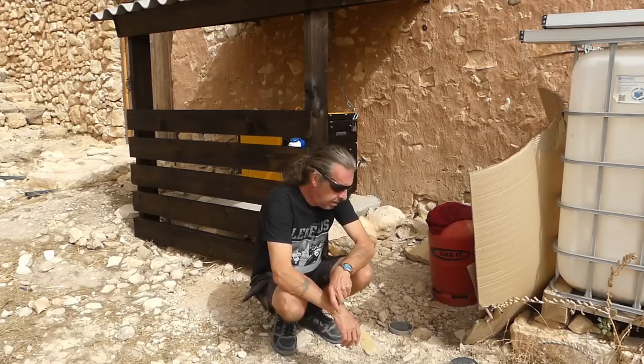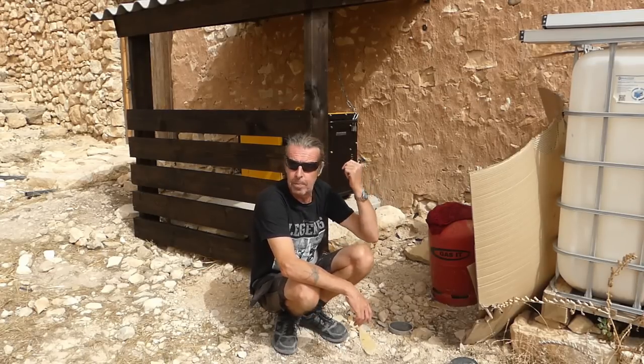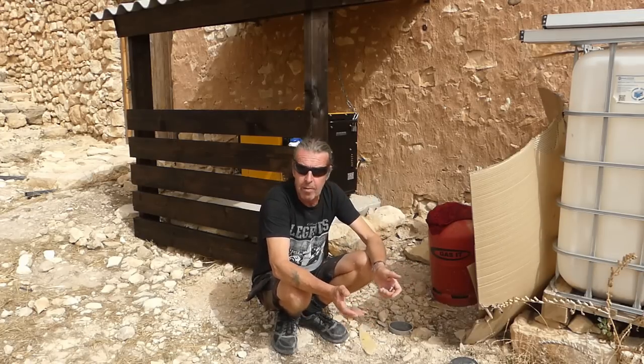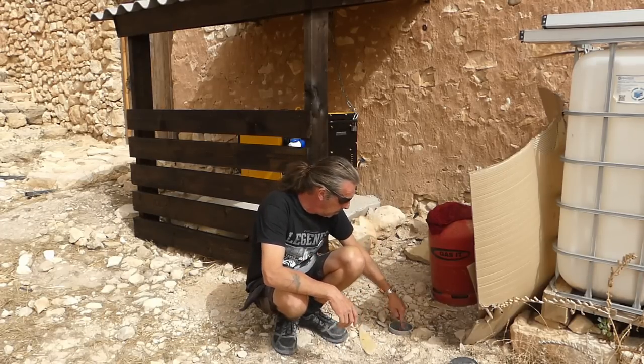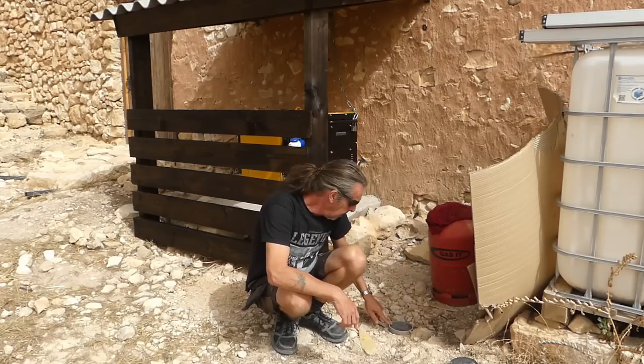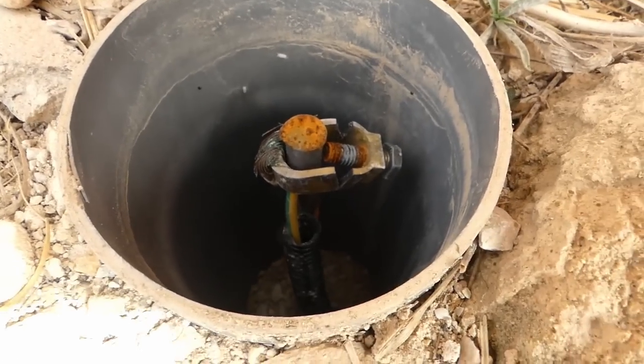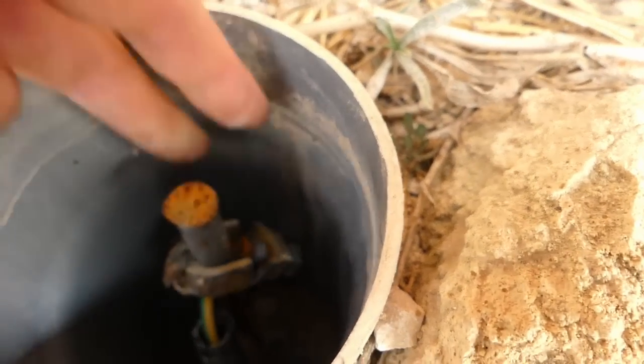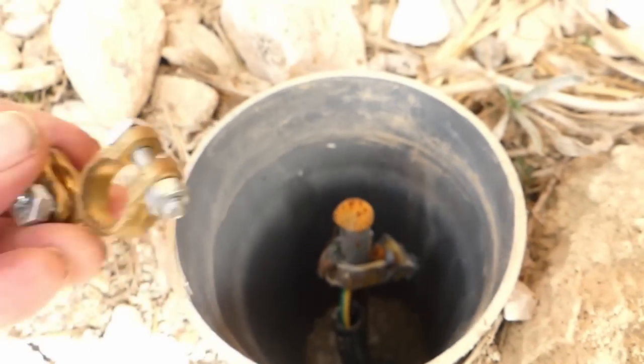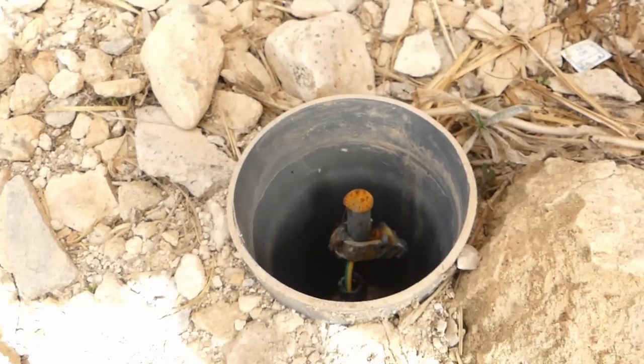There's not an awful lot I can do until the inverter actually comes, but things like the generator, the battery, and the new inverter inside all need to be ground bonded or earthed. So just as a matter of interest, this is our fairly big rod that goes very deep into the ground. I just thought I'd have a quick look at it and I couldn't believe what I saw - the thing that holds the earth to the rod is snapped. So I need to change that. What I'm going to do is put a battery terminal on it round the rod and fix the clamp to that.